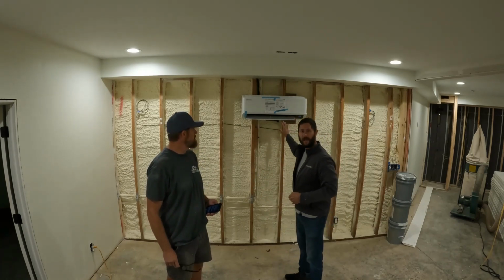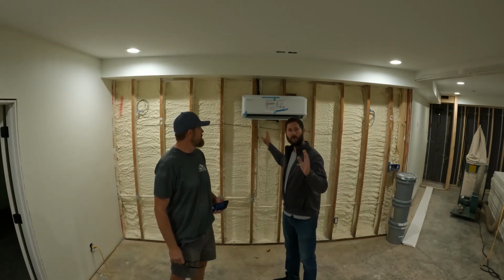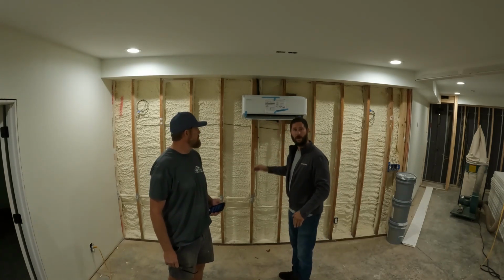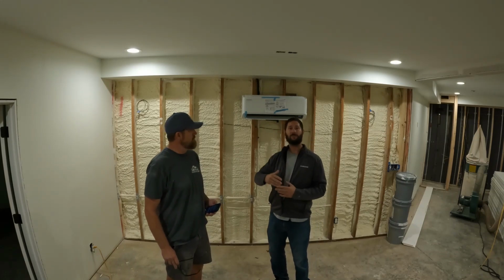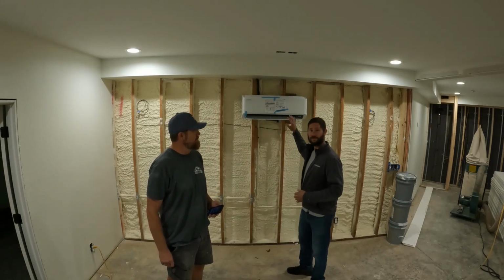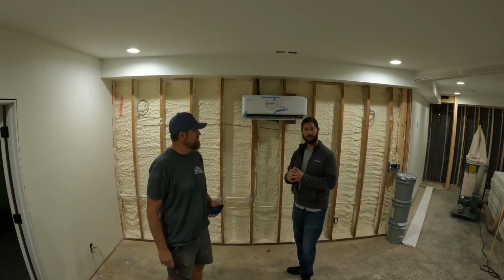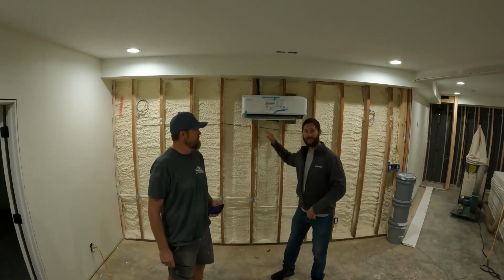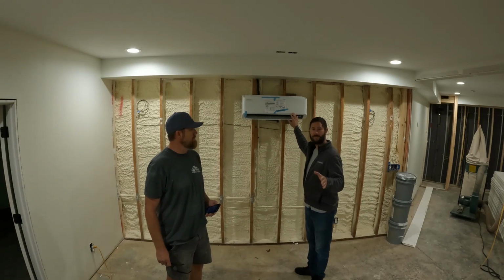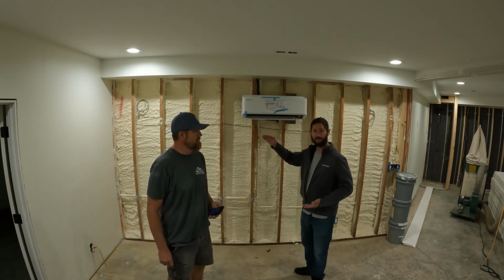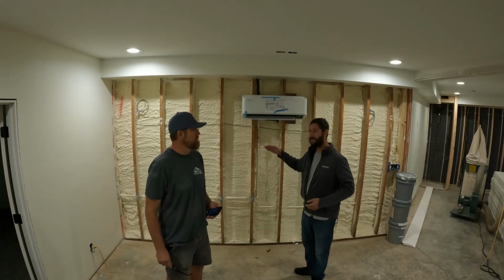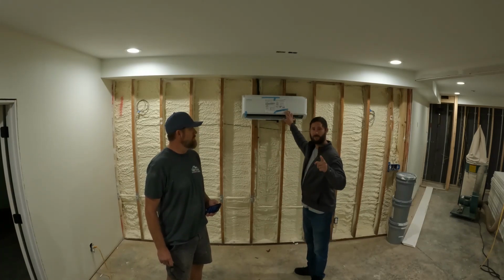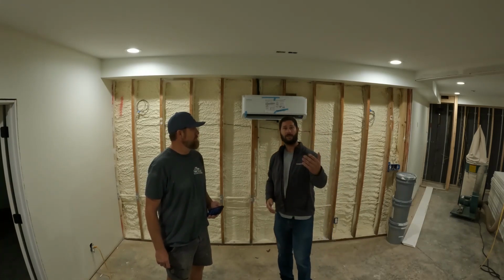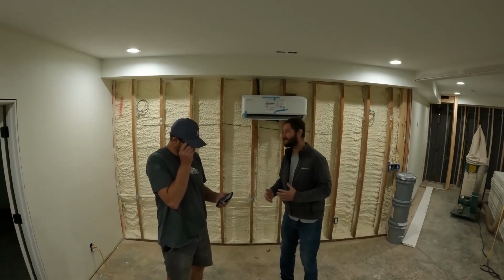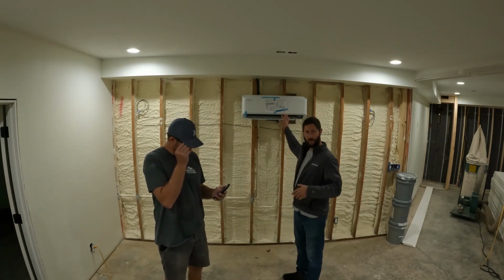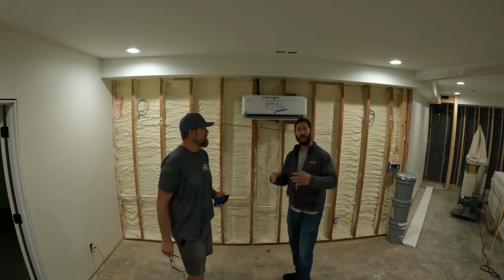So we're not always going to have 95-degree days, and when we don't, this equipment has the ability to go from 30% upwards of 130%. So even though I've installed a 1-ton unit right here for this section or this area of the home, it'll actually go down to around 3,000 BTUs, and it'll go up past 12,000 BTUs, around 18,000. So that's one reason I choose mini splits over traditional ducted, because of their ability to modulate. This is a modulating heat pump, so you're able to save energy on those days where it's not 95 degrees.